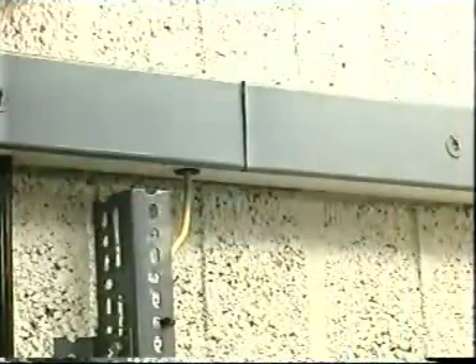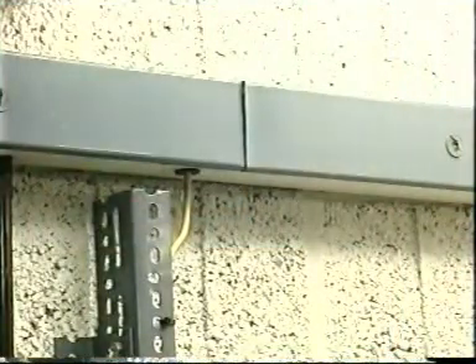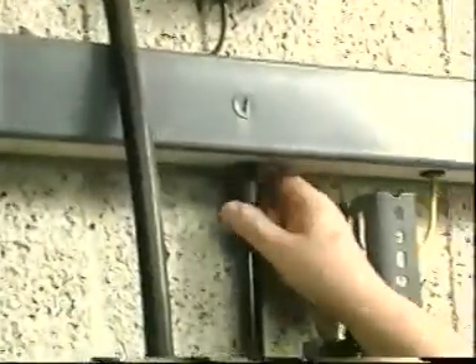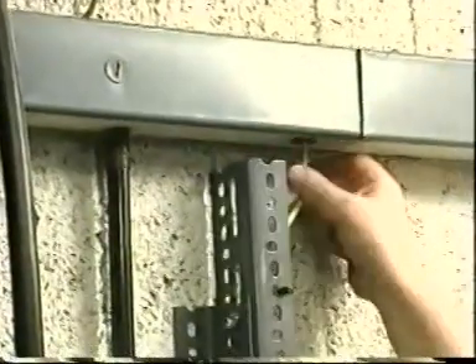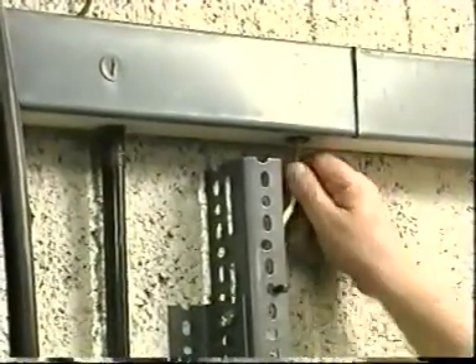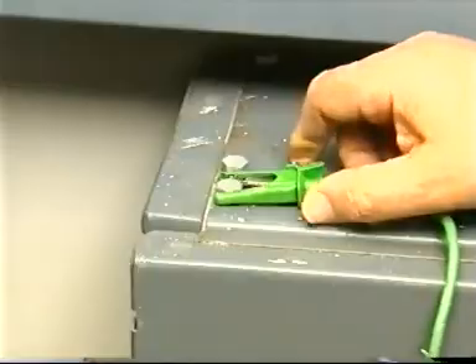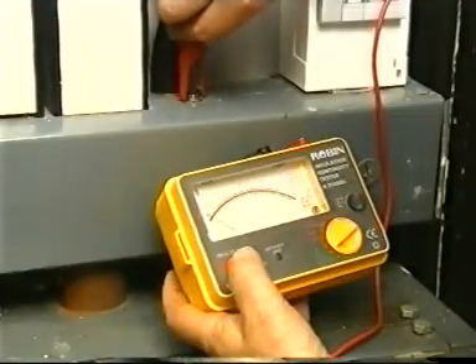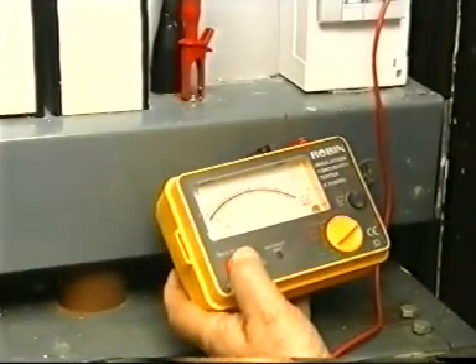Metal conduit and metal trunking have in the past been commonly used as a sole circuit protective conductor. Such enclosures should periodically be given thorough inspections, as many will be found to have not stood the test of time. A low ohmic test can be carried out on the protective conductor circuit with suitable test equipment.